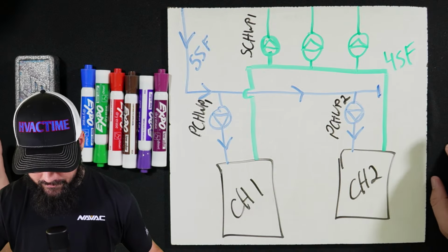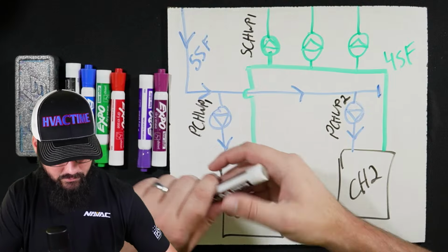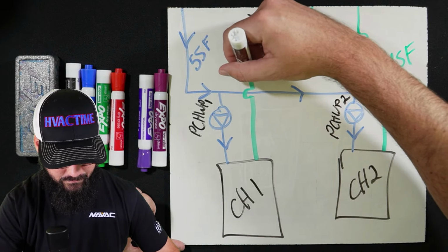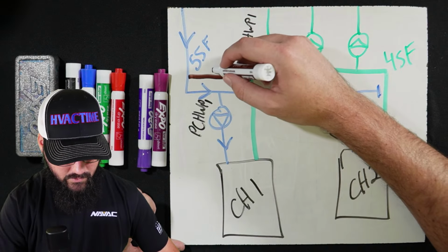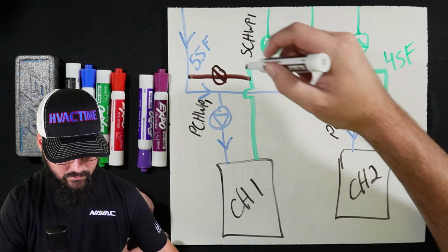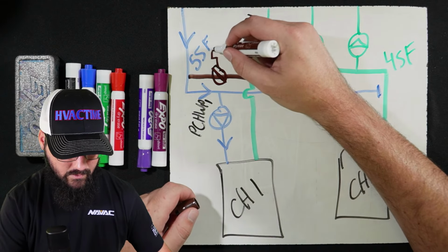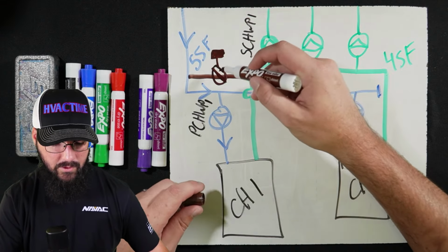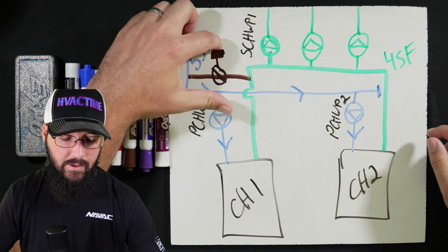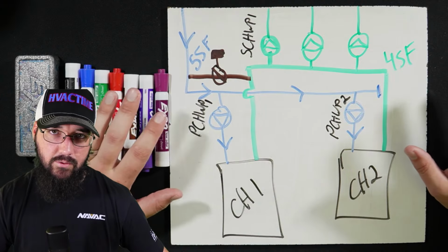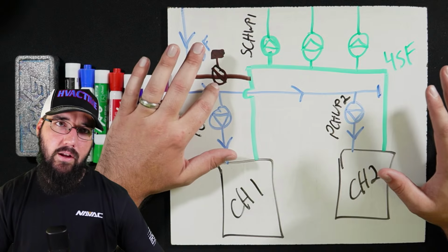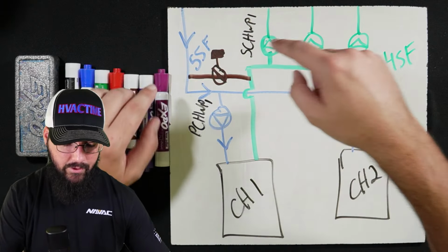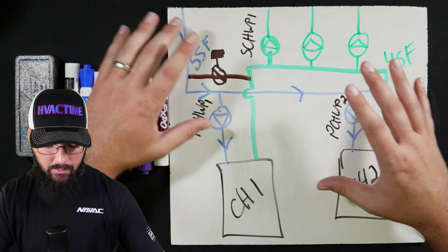Oh, there should be a bypass here. Yep. Let me get the bypass. One second. Almost forgot that. All right. We're just going to draw a simple valve. If you're looking at a schematic and it's got the little stem with the colored-in square, this means an actuator. Depending on the symbol, that changes the type of valve. I think this could be a butterfly. Is that right? No, the butterfly is different. Anyway, actuator. So this is a bypass. This is how we regulate the flow between the primary and the secondary.